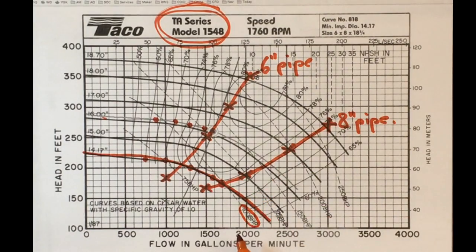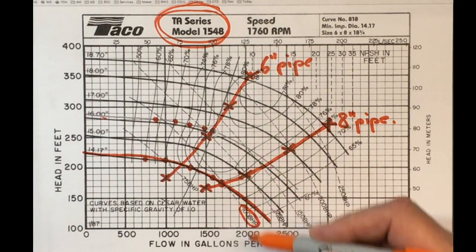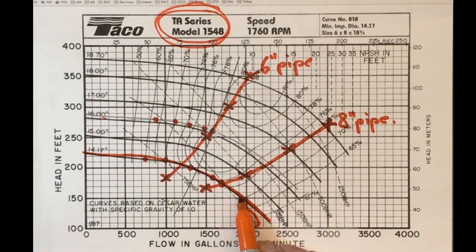And as long as we stayed below this line, we'd be fine. But if we ever use this pump at a higher flow rate, we're going to require more than 100 brake horsepower to drive the pump.